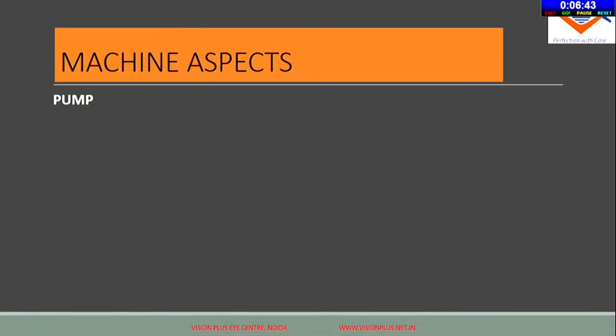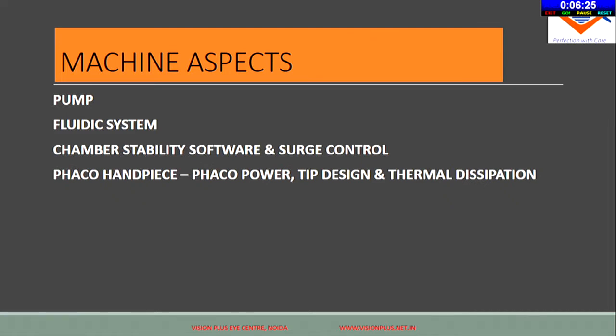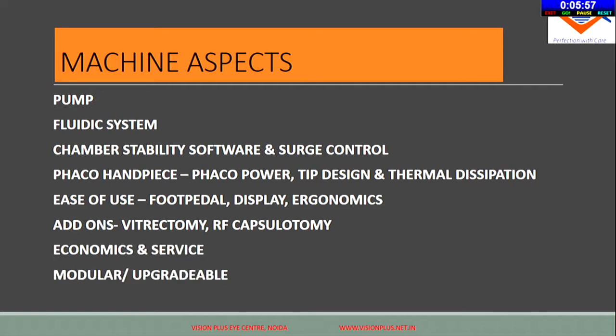Aspects to look at: first, the kind of pump. Look at what type of pump is available in different machines — the fluidic system, chamber stability software, and surge control, which adds safety to your surgery. Also look at the phaco handpiece options, the power modulations, tip designs, ease of use, whether it has a display, whether the foot pedal is wireless, ergonomics, how it fits into your OT system, add-ons like anterior or posterior vitrectomy, economics and service, and whether it is a modular system you can upgrade over time.